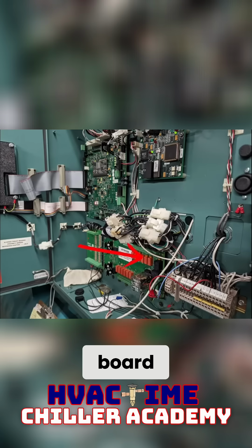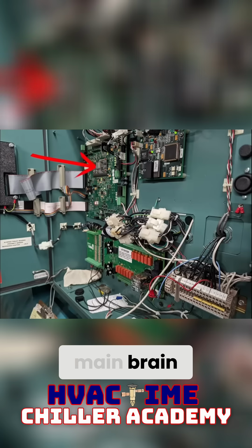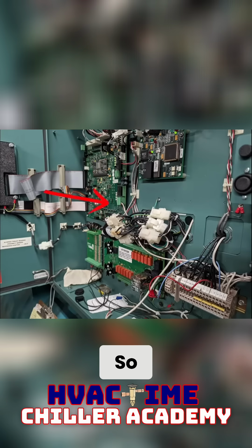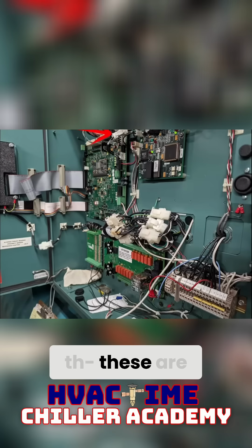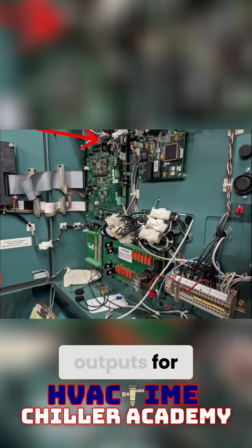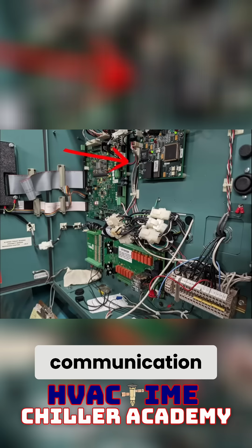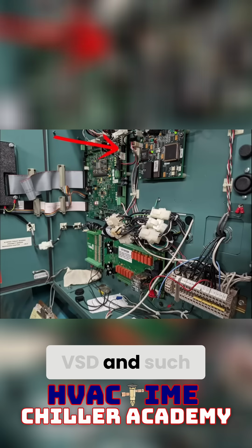This is your I/O board. So this is your main brain. This right here, this processor, is actually the processor that runs the entire chiller. So these are still inputs and outputs for this module up here. Now these are your power rails. This is communication going through your ACC and VSD and such.